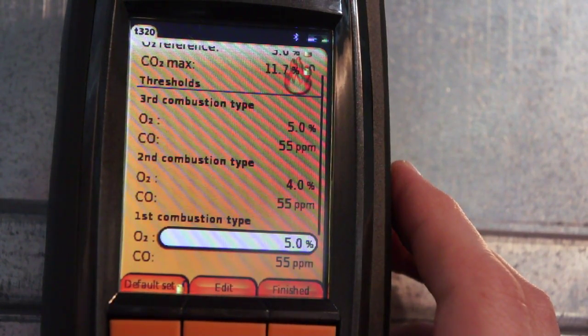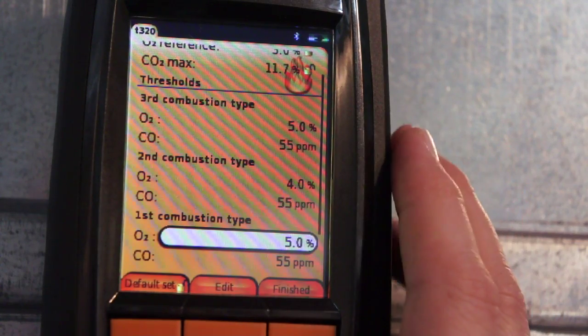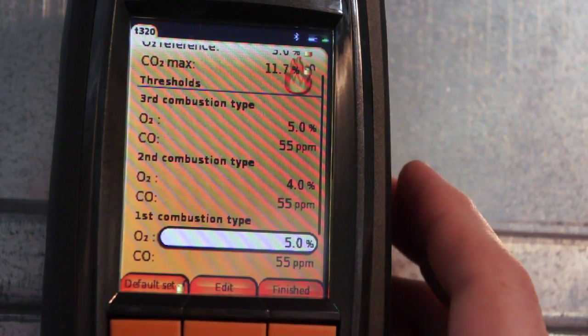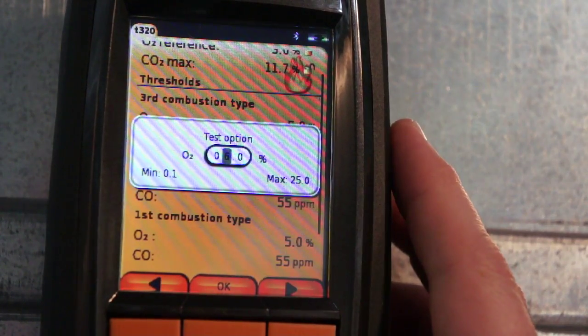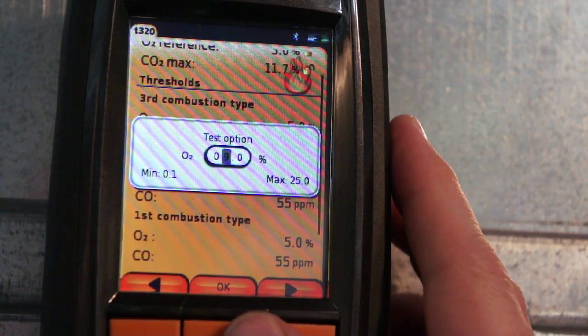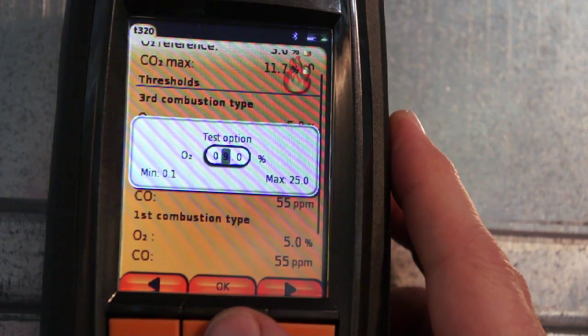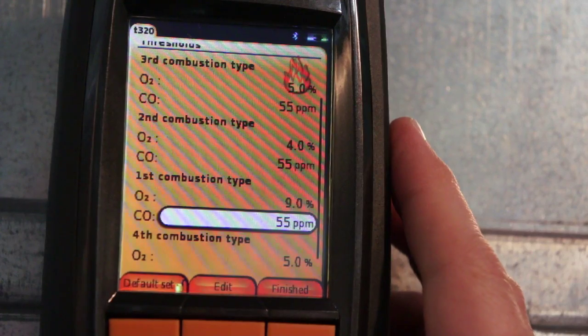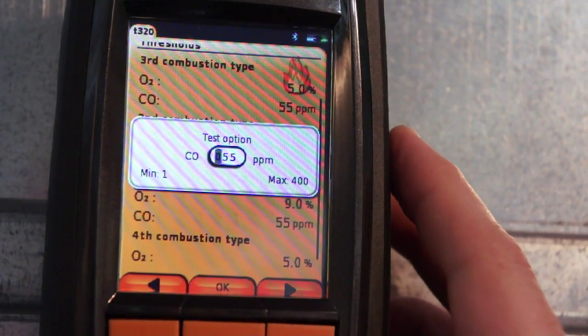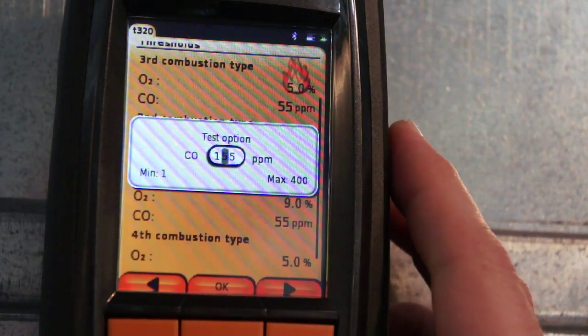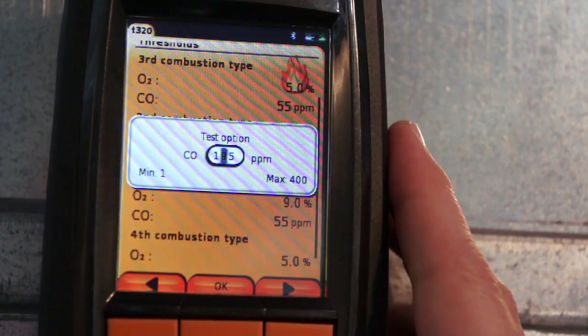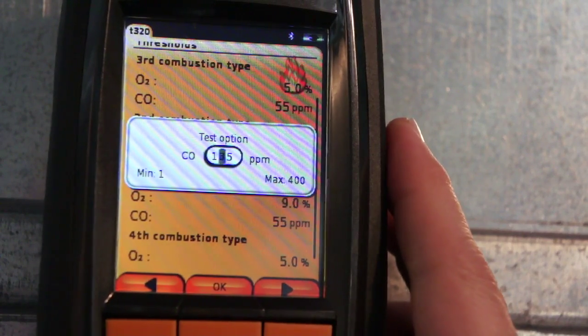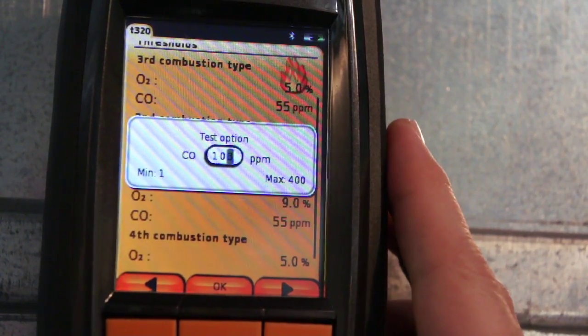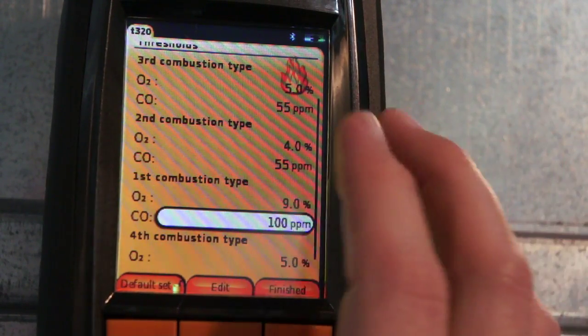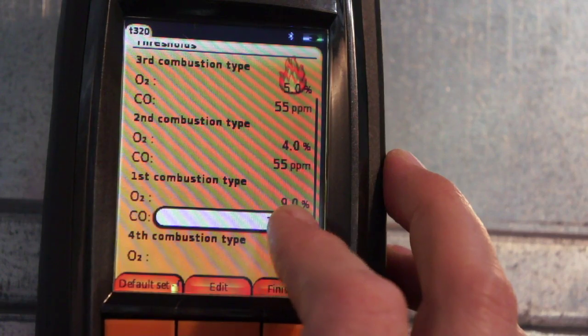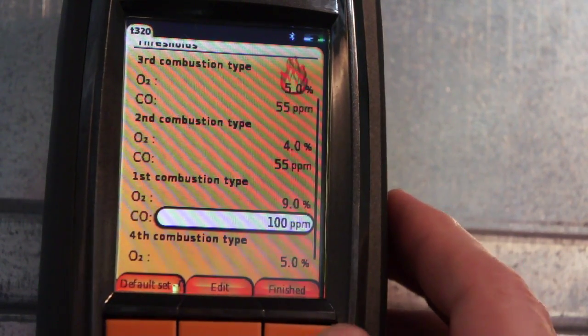So I'm going to adjust my first combustion type. On this 90 plus, I typically would not want to see an O2 above 9%, so I'm going to go ahead and edit that, and I'm going to take this up to 9% on the excess air, which would be probably around 75% excess air if I'm thinking right off the top of my head. I'm going to hit OK. And I want my CO to be optimized at 100 parts per million. So I'm going to hit the up key once here, that's 1. I'll take these down to 0, and 0, and 0, hit OK. So now I'm optimized for this combustion zone. Maximum O2 I want to see is 9%, CO 100, and I'm going to hit finished.